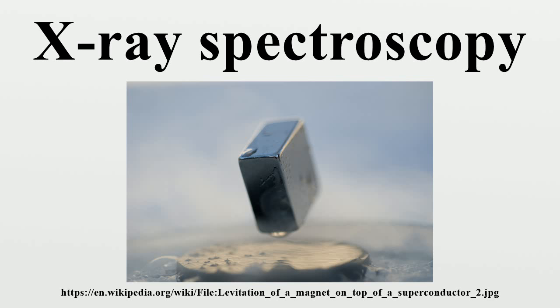Spherical grating mounts. Henry Augustus Rowland devised an instrument that allowed the use of a single optical element that combines diffraction and focusing: a spherical grating. Reflectivity of X-rays is low regardless of the used material, and therefore grazing incidence upon the grating is necessary.